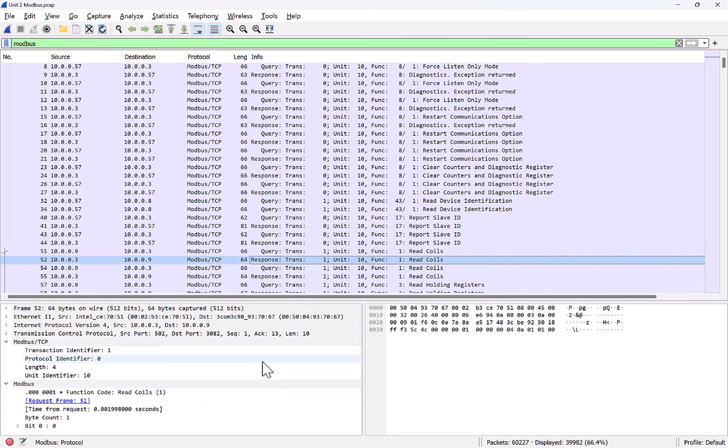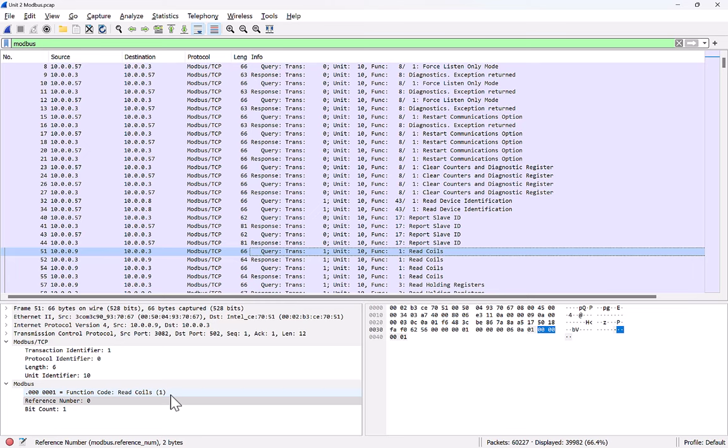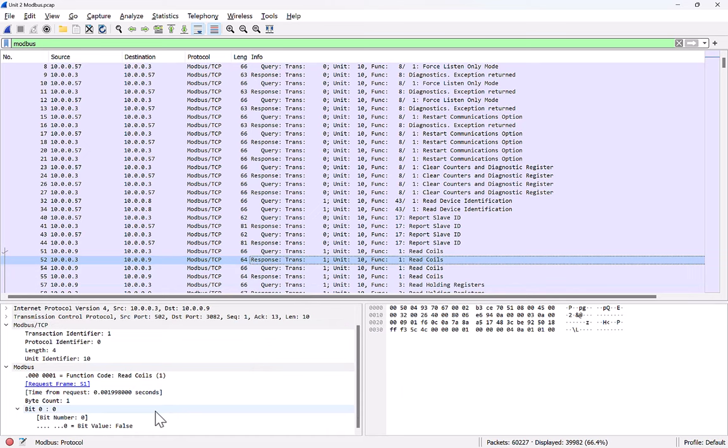the PLC in this case is going to look up what is the value in that first slot. And it's going to send that value back and say, the value is 0. Remember, a coil can only store a 0 or a 1. So we're expecting a 0 or a 1. So we issue the query to say, what's the value in the first coil, essentially? I'm kind of shortcutting it, but we're just saying, what's the value in the first coil? And then the PLC is coming back and saying, the value is 0. So maybe in that case, that means the air conditioner is off.